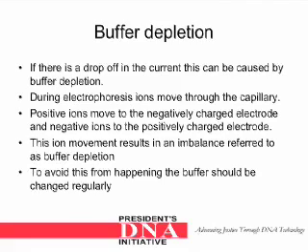Buffer depletion: if there is a drop-off in the current, this can be caused by buffer depletion. During electrophoresis, ions move through the capillary — positive ions move to the negatively charged electrode, and negative ions to the positively charged electrode. This ion movement results in an imbalance referred to as buffer depletion. To avoid this from happening, the buffer should be changed regularly.